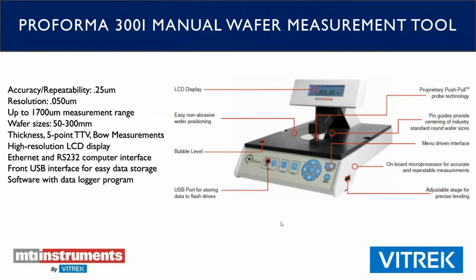So it does thickness, 5-point TTV, which is total thickness variation, and center bow measurement. As you can see, it does have a high resolution LCD display. There's also Ethernet and RS-232 computer interface. There's also a software data logger program. So if you have a stack of wafers that you're testing, you can store that through the computer program if you want to, or through the front USB port to save your data. There's also these little pin guides which help you center your wafer if you're making a bow measurement. That is what that is for.